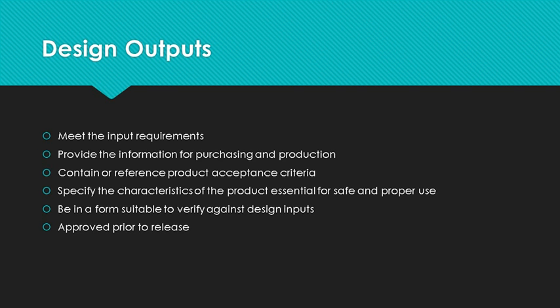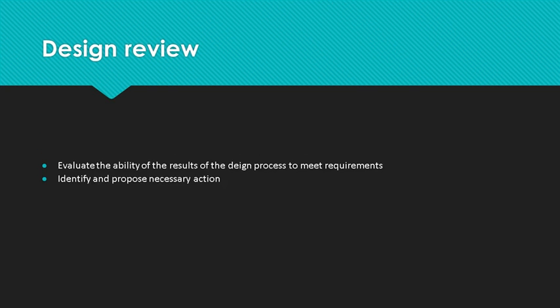In between defining the design inputs and producing the design outputs, the design will be reviewed at intervals defined in the design plan. The purpose of the design reviews is to evaluate the ability of the results of the design process to meet requirements and identify and propose necessary actions. So are you going to go on? Have you met the requirements to this point of the design? If not, what do you need to do to meet those requirements?